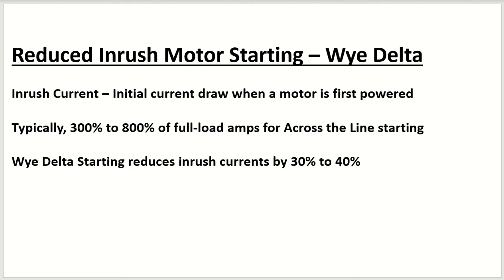In this video instruction, I want to talk about a form of reduced inrush motor starting called Y delta. Inrush current is the initial current draw of the motor when it's first powered, and typically the inrush current is 300 to 800% of the full load amperage of the motor when you start the motor across the line with full voltage right from the start. If you use the Y delta starting method, that reduces the inrush current by 30 to 40%.